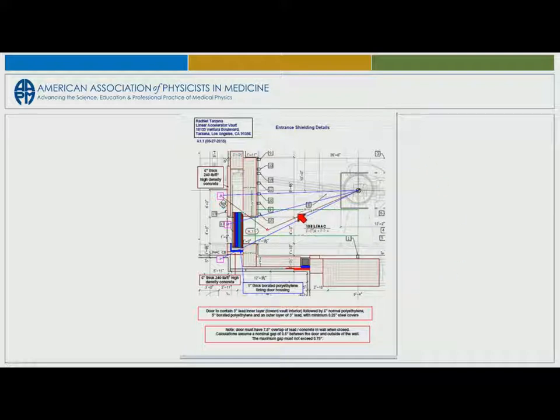Then you give very good details of what goes in that door and what we call the details around the sliding door, how much it has to overlap. You want hopefully at least 9 inches of overlap for each one of these sides of these doors, because otherwise what happens is your primary beam comes right through here and misses the door and goes through there with no shielding.